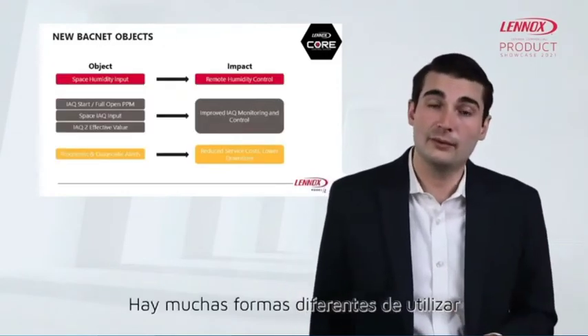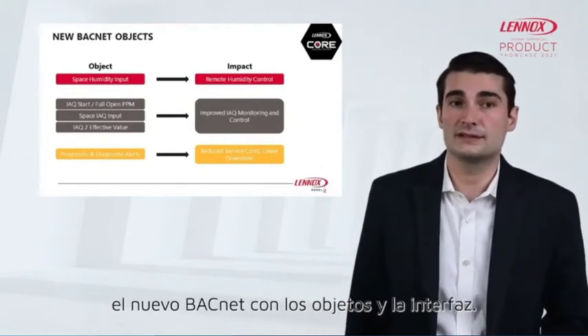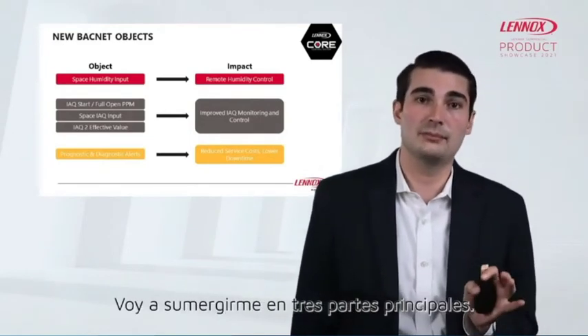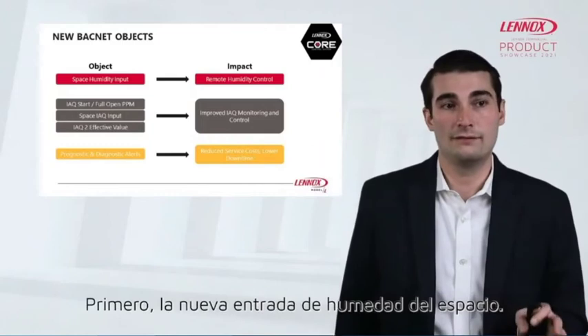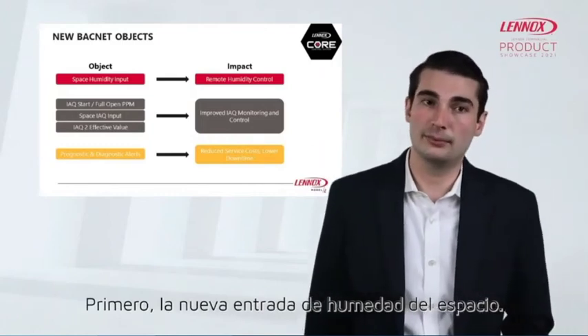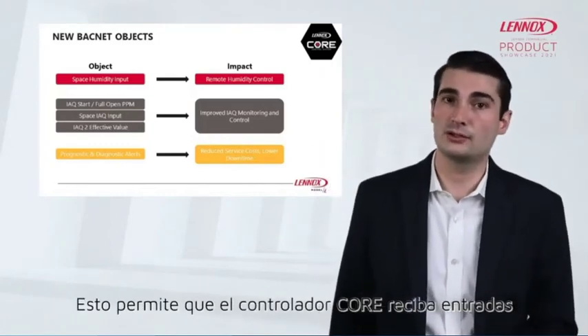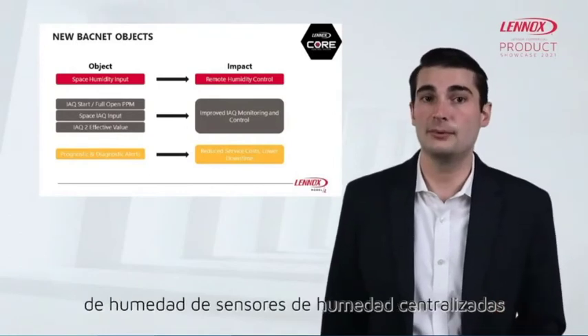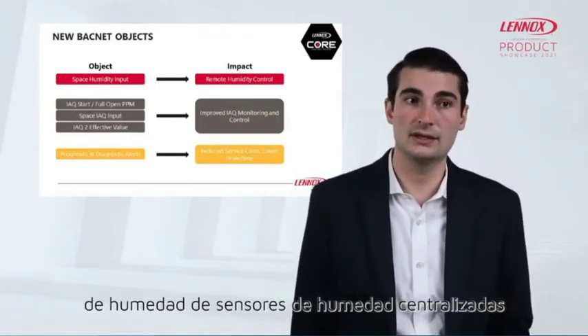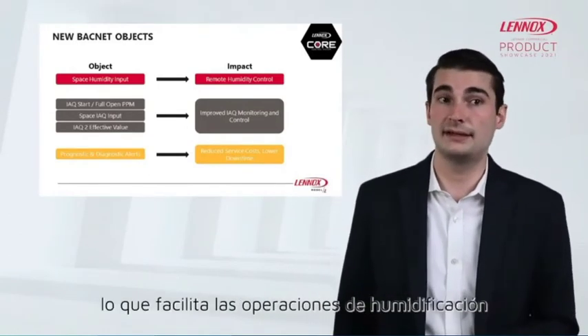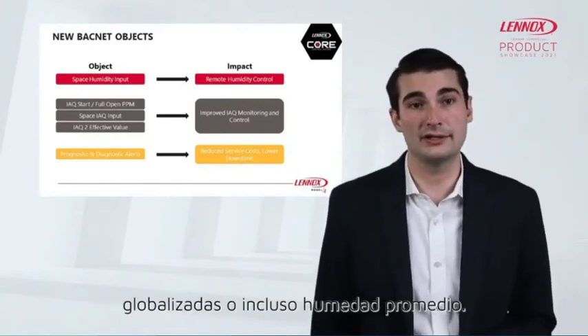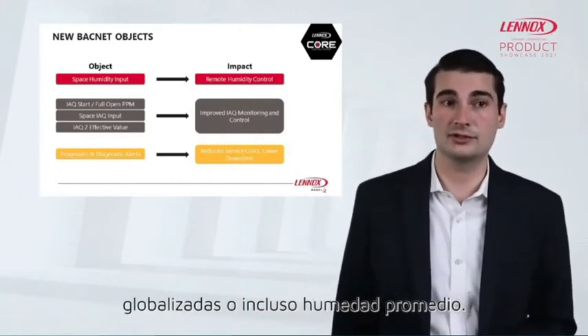While there are many different ways to utilize the brand new BACnet objects in the interface, I'm going to dive into three main parts. First, the brand new space humidity input. This allows the CORE unit controller to receive humidity inputs from centralized humidity sensors elsewhere in the building, facilitating globalized dehumidification operations or even humidity averaging.